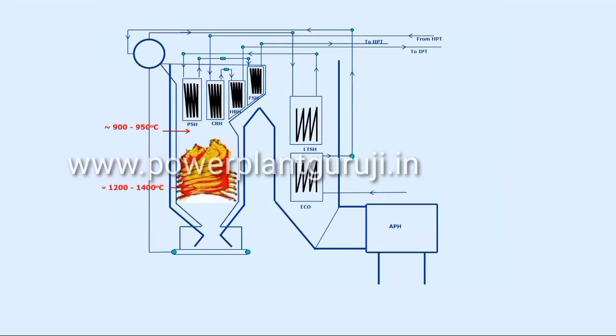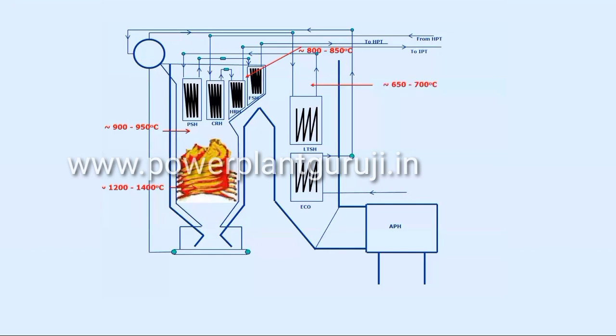Before the final superheater, the temperature comes to around 800 to 850 degree centigrade. Then what we call the FEGT, the furnace exit gas temperature, which is basically the LTSH inlet temperature.